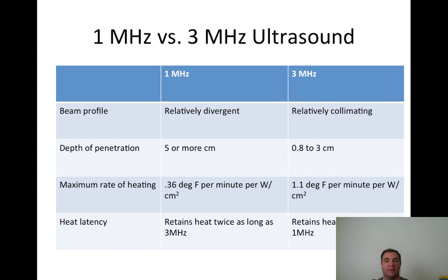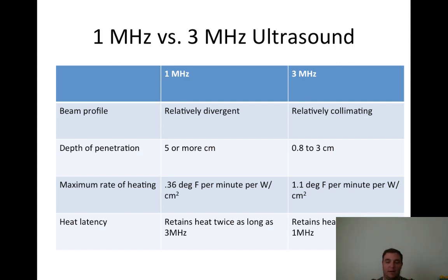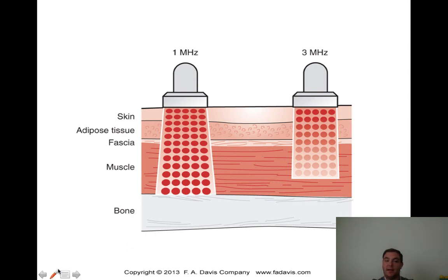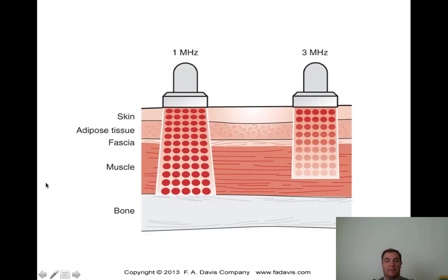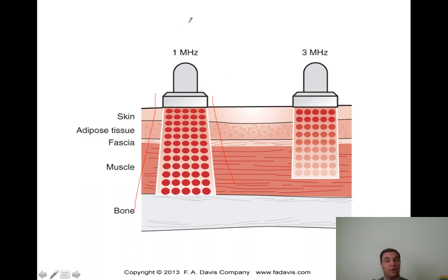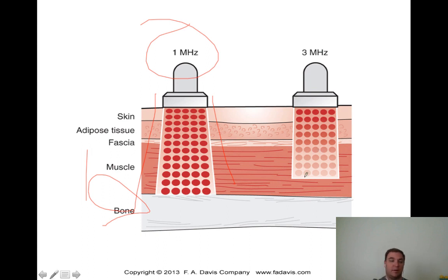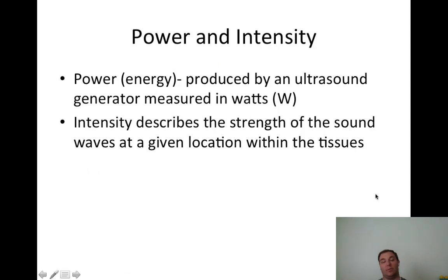To clarify: one megahertz is divergent, more cone-like; three megahertz is more collimated. One megahertz goes deeper - all the way to bone - versus three megahertz which may only go halfway through the muscle. Power is measured in watts; intensity describes the strength of sound waves at a given location within tissues. SAI describes the amount of energy passing through the sound head's ERA, expressed in watts per centimeter squared.